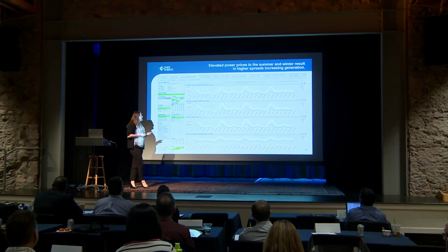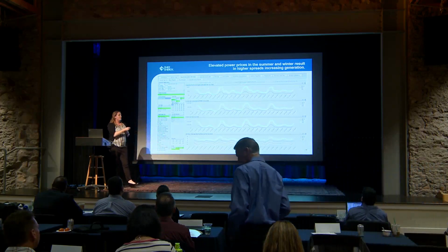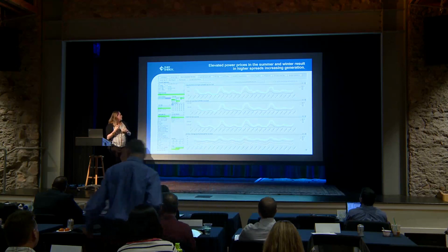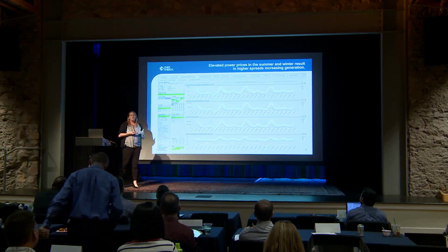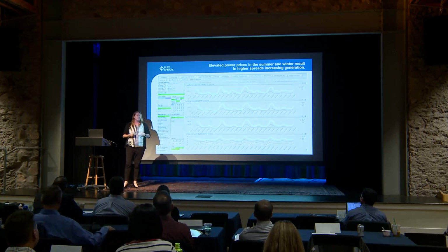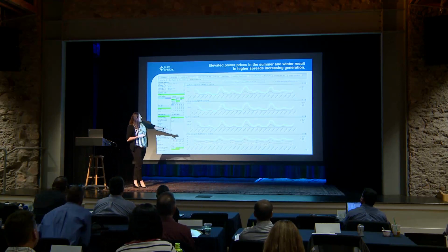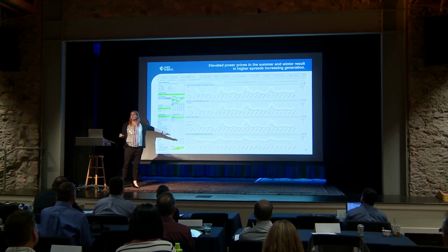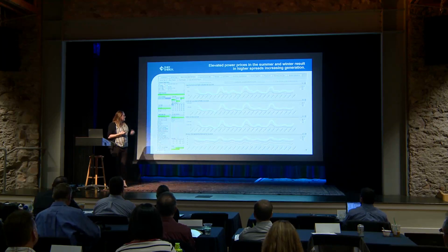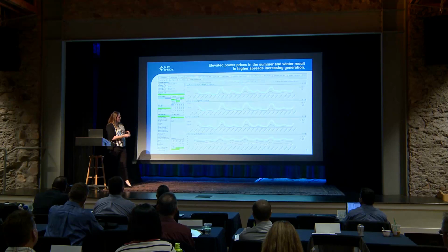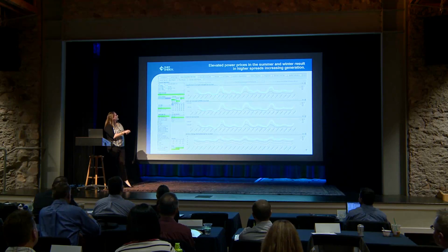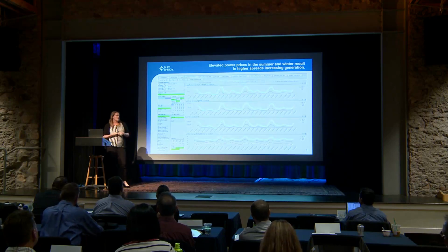So what I've shown here is a plot for, you can either look at generation if you clicked on this tab, or capacity factor. But you wanted to view that in terms of, what's the capacity factor, what's the fuel consumed, what's that total cost. So if those don't align, you could say, well, maybe there's something wrong with my dispatch. And then the fourth plot, I've allowed them to actually choose another variable of interest that they may want to look at. So in this case, I've chosen, well, is the unit in the money or not, since this is a dispatch to price. So when you're more in the money, your capacity factor is higher, which obviously you're consuming more fuel and your fuel cost is going up.